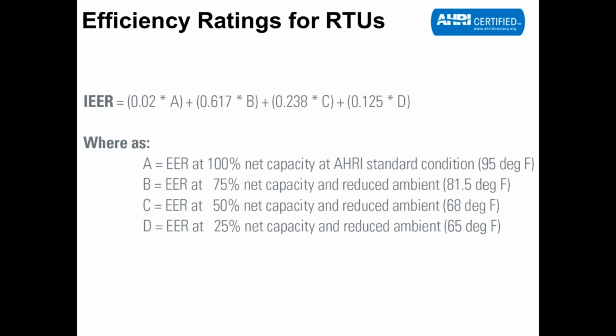The way IEER works is they actually test it at 4 different points, or they rate it at 4 different points. One of those points, point number A, is the traditional 95-degree max capacity, EER type number. Then they do the same kind of test, part loaded at 75%, 50%, and 25%. Then they heavily weight the 50 and 75% numbers. The 100% and 25% numbers get very little weighting because the 100% number hardly ever happens, and at a 25% number I should have some assistance from the economizer at that point. So really all the weight goes towards the middle.